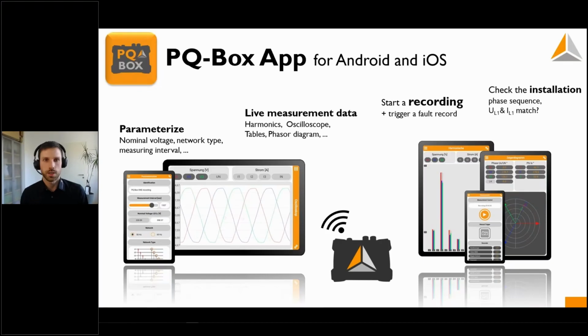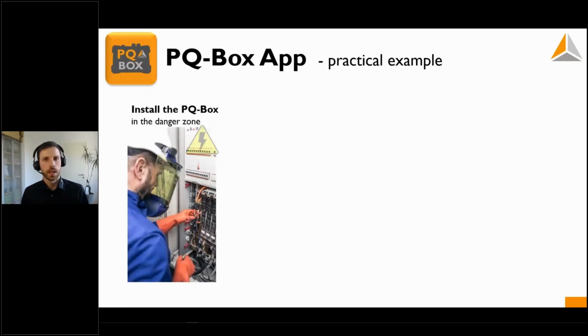And you can always check the installation. Is the phase sequence correct? Does phase 1 of the current match phase 1 of the voltage? And here I give you one very practical example of when to use it and why. So let's assume you install the PQ-Box in a danger zone. There is a voltage. You can access the dangerous voltage. The whole environment is dangerous. So please take care. Only skilled people should perform the installation.